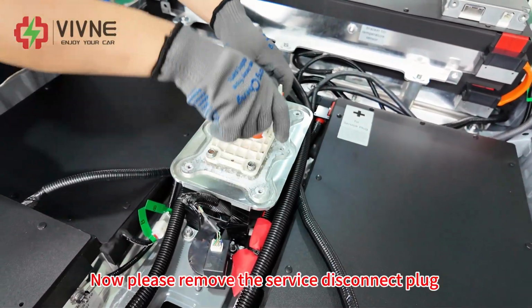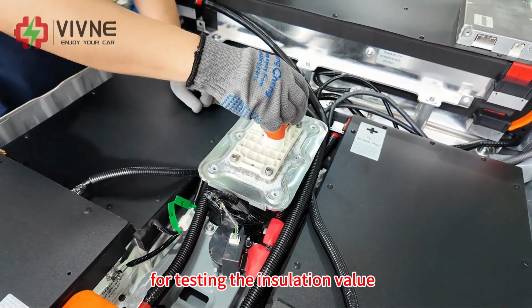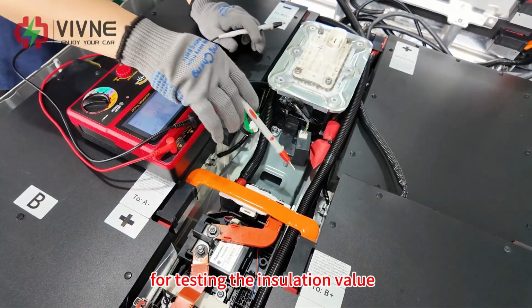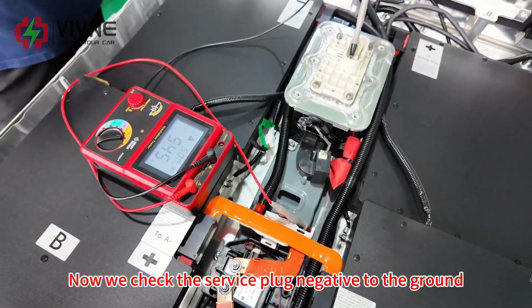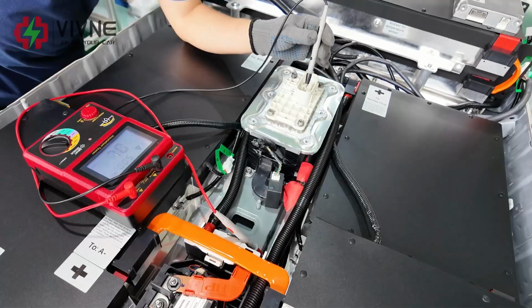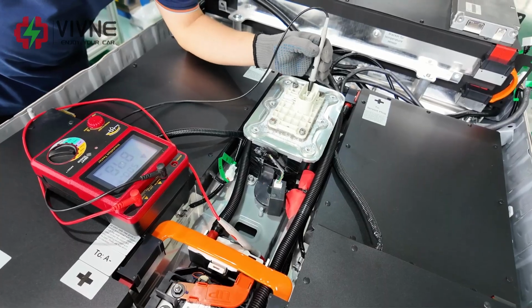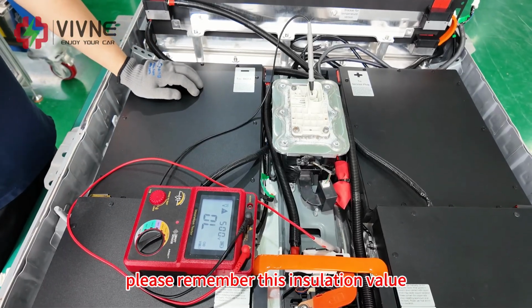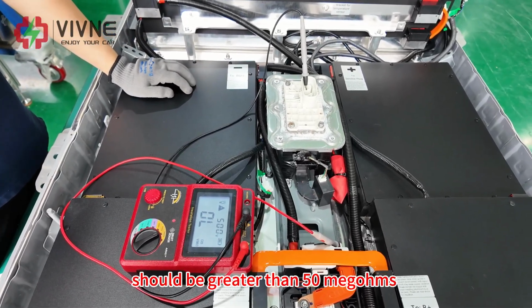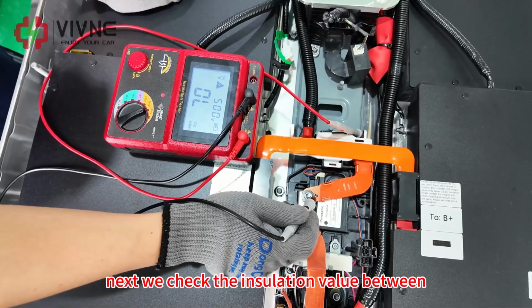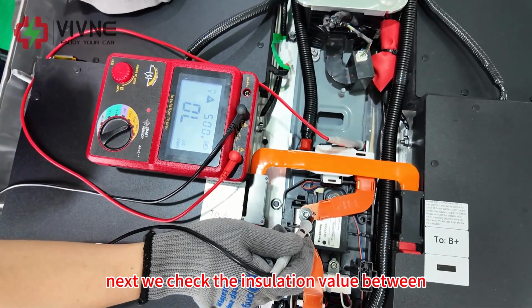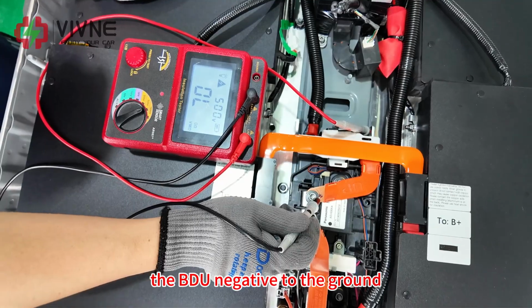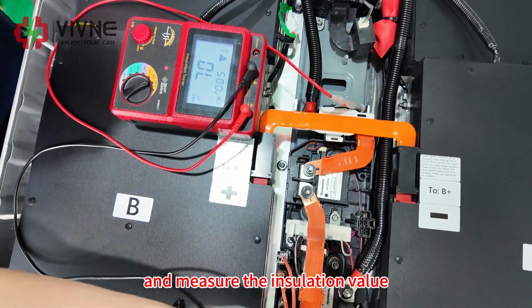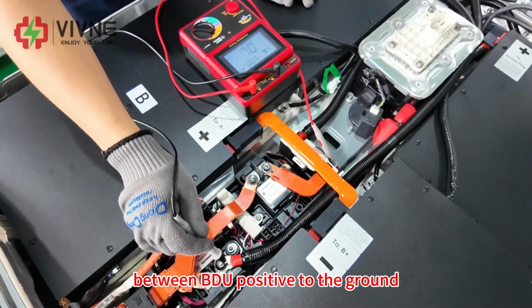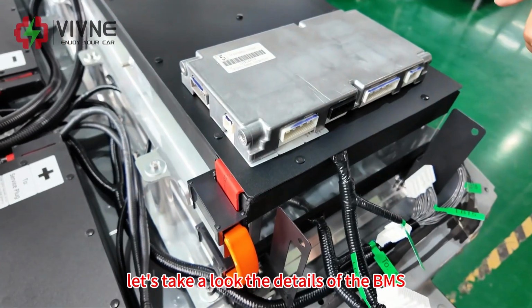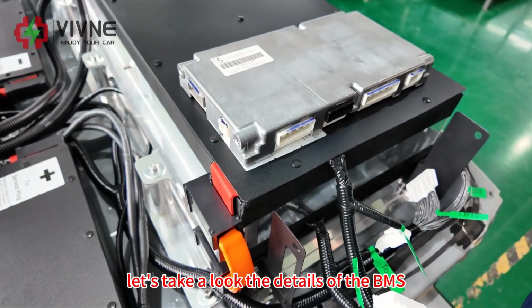Now please remove the service disconnector plug to test the insulation value. Now we check the service plug negative to the ground. Now we check the other end. Please remember this insulation value should be greater than 50 megohms. Next, we check the insulation value between BDU negative and the ground, and measure the insulation value between BDU positive and the ground. Let's take a look at the details of the BMS.